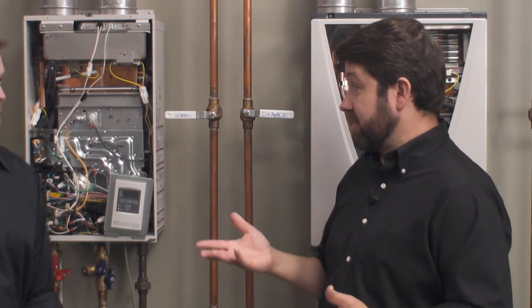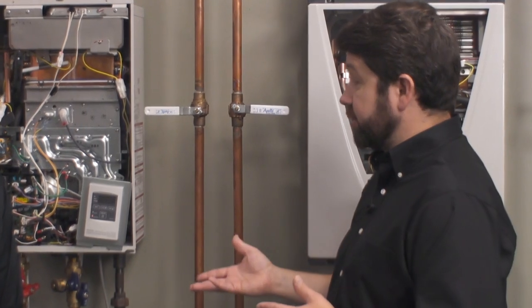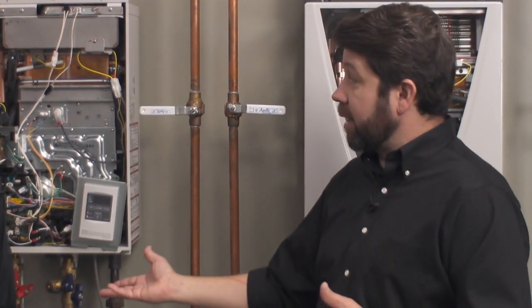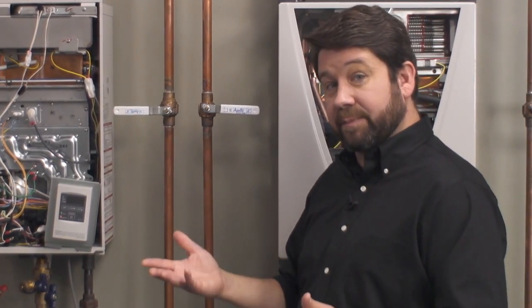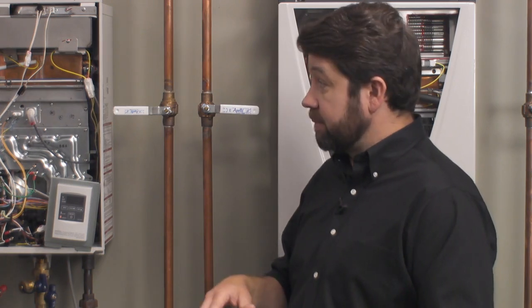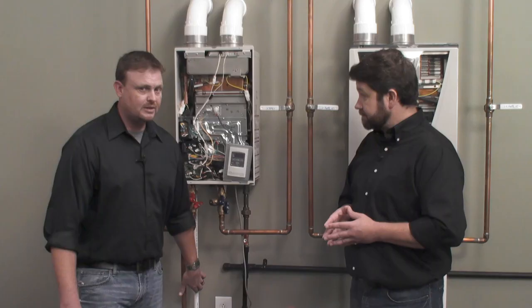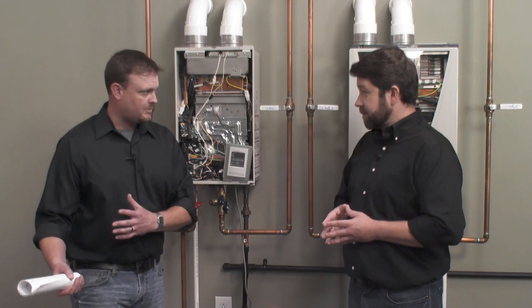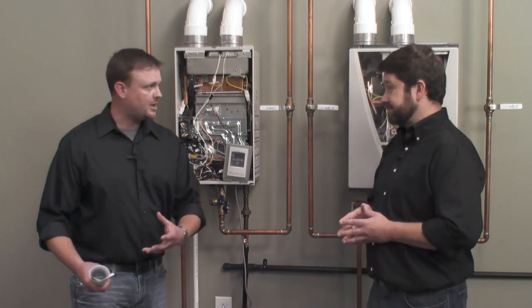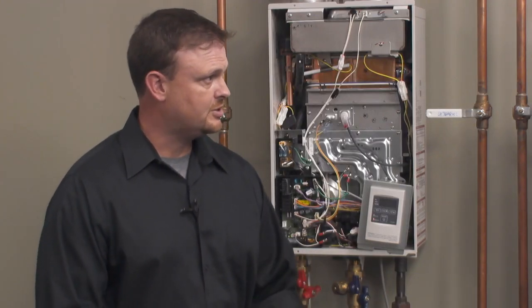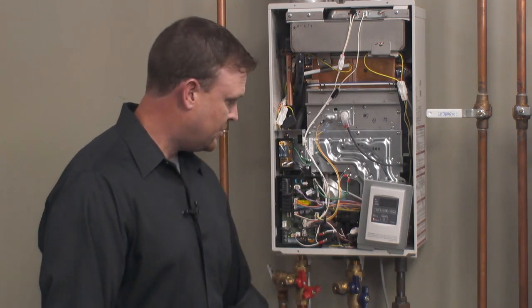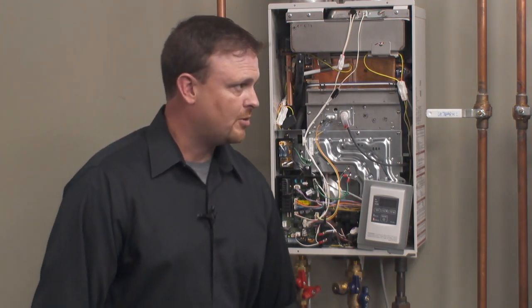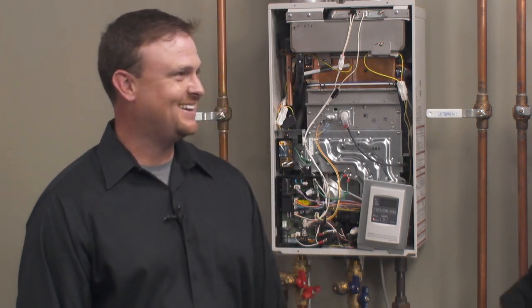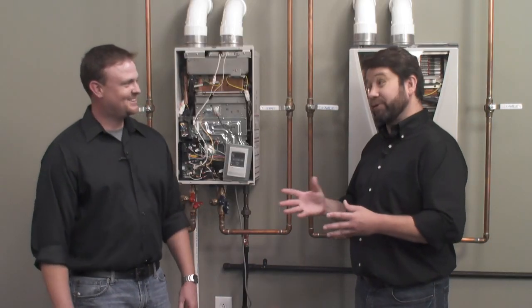Now, if we have to take it into a metal drain, we do offer a neutralizer kit that goes in line there, and it's got a media in there that takes that acidic pH down to a more neutral pH. Now, let me talk to you about that, because this is not like the condensation on the heat pump. Yeah. This is actually acidic, because the flue gas is actually turning into liquid. So you wouldn't want a nice shiny copper line. You'd want PVC. Yeah. Not for the condensate line. A nice shiny copper line looks great for an installation, but the acidity in the condensate will actually eat through that in a short period of time.